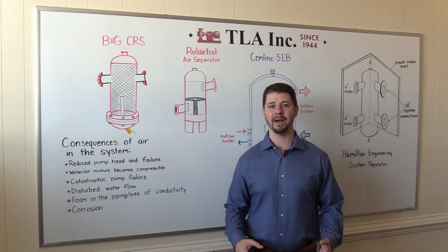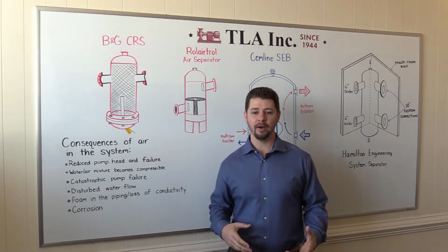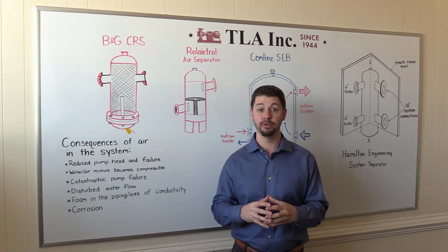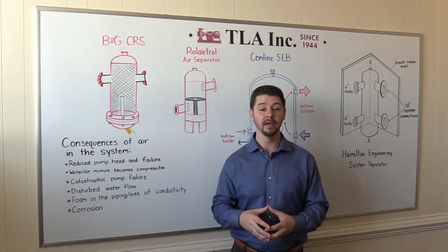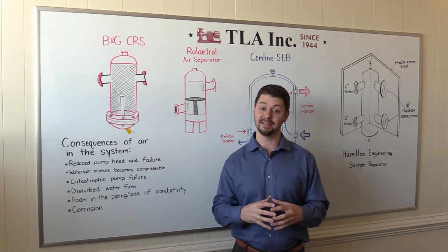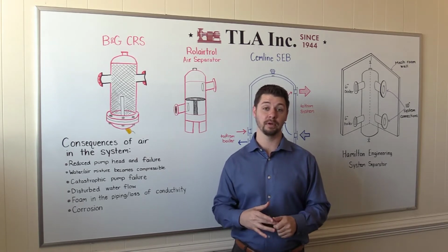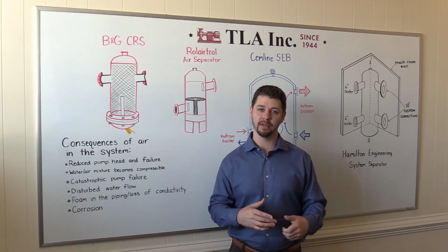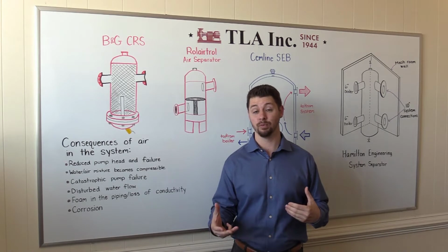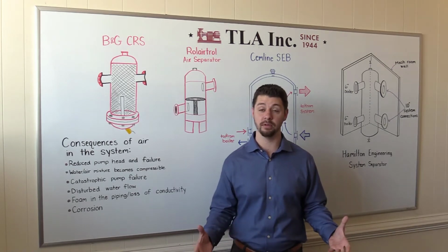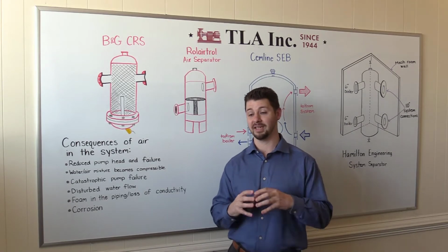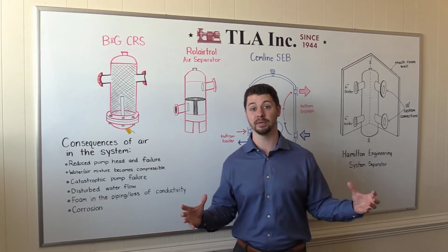This time we're going to talk about air and water. Now, air that is contained in water is mainly described by two different laws, Henry's law and Stokes' law. And the primary two reasons for air getting entrained in water is temperature and pressure. Now, within a closed hydronic system, velocity has something to do with that as well. But the combination of those two laws allows us to get a better understanding of how much air can get stuck in water and how do we release it.